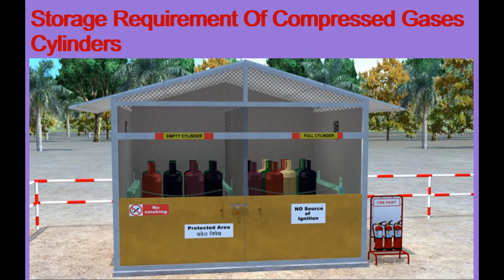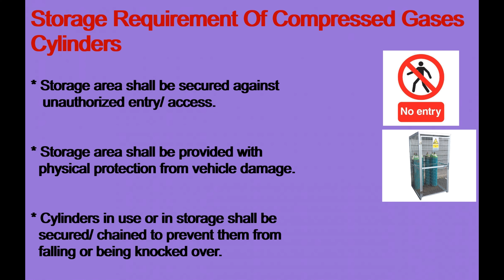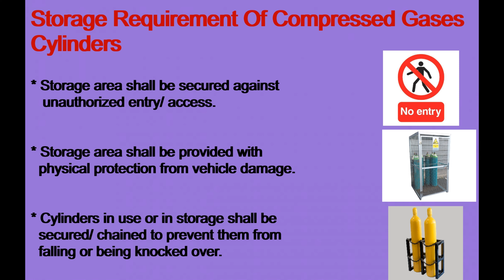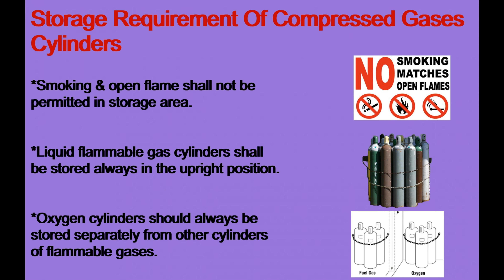Now we will see the main storage requirements for compressed gas cylinders. The storage area shall be secured against unauthorized entry and access. Storage area shall be provided with physical protection from vehicle damage. Cylinders in use or in storage shall be secured, chained to prevent them from falling or being knocked over. Smoking and open flame shall not be permitted in the storage area. Liquefied flammable gas cylinders shall always be stored in the upright position. Oxygen cylinders should always be stored separately from cylinders of flammable gases.